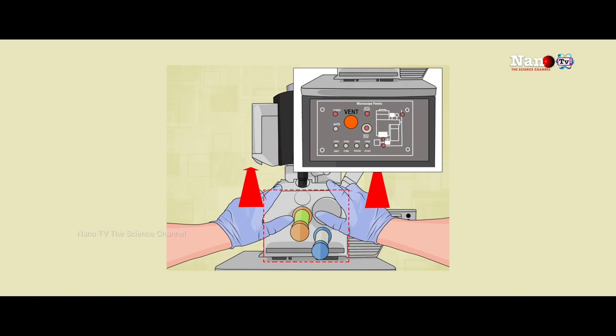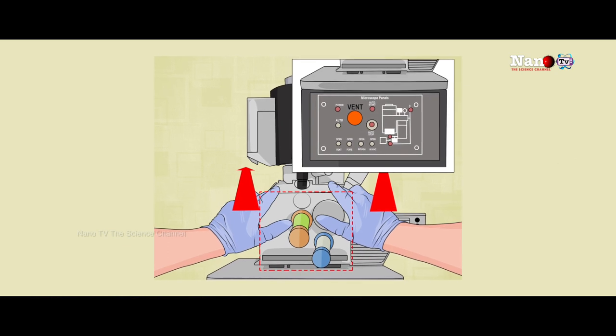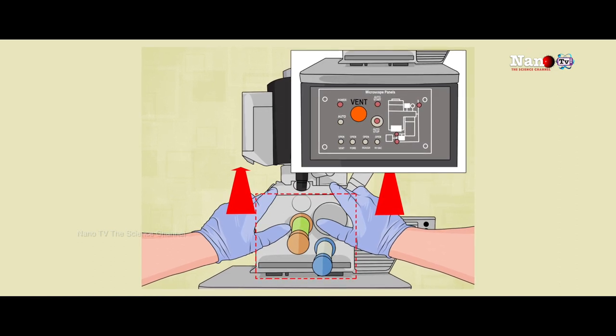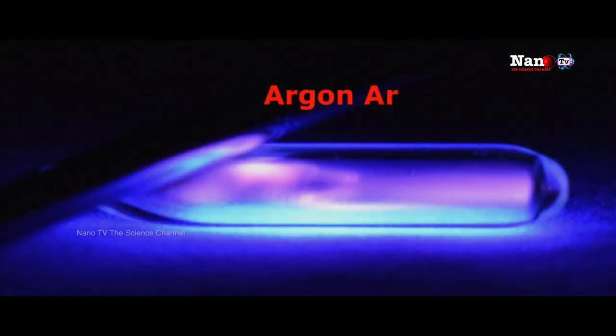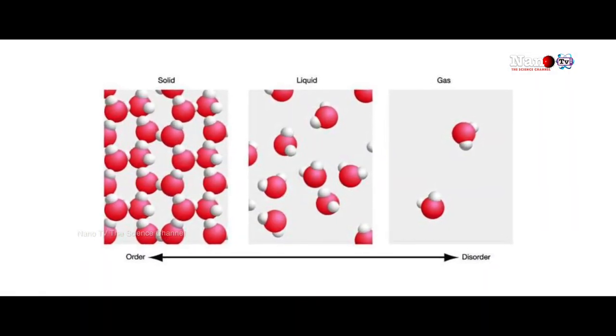This is a technology invented about 30 years back. For non-conducting and non-evaporating samples which are not purely vacuum-oriented, a gas is introduced inside the chamber near the sample area. If you introduce argon gas or water molecule gas, which are neutral in the beginning, they get bombarded by incoming electrons and dissociate into positive ions. These positive ions come near the sample surface. For non-conducting samples, charge has already accumulated so electrons cannot pass through the sample.